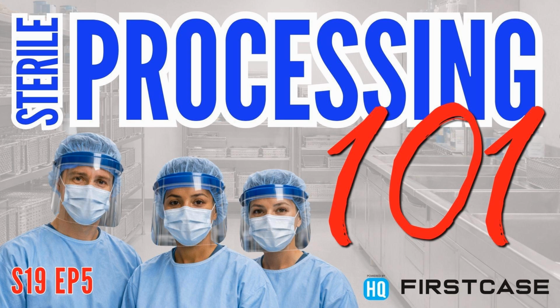Yeah, so the big issue is, water does a great job at communicating that heat and transferring it from the steam to the instrument. But that's not the only thing water does a really good job of transferring. It also is a really great pathway for microorganisms to move through. And so because of that, if you have a package that gets wet, then we reject it in the OR, right? Because that water can become a pathway through the packaging to the instrument and can contaminate the instrument.